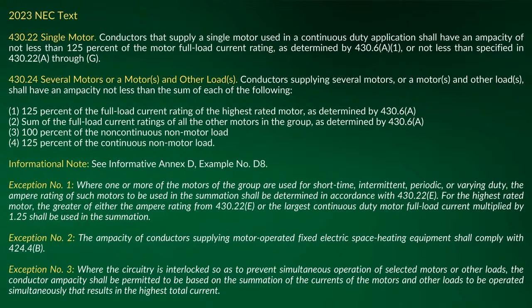Now we're going to look at the overcurrent device and see what it says. If I look at 430.22, I'm sorry, this is supposed to actually be 430.62 up top. I just didn't delete that first line up there. I was working on this at 3 and 4 in the morning last night, trying to get all this together. The haters are gonna destroy us over that. Now, if you look at 430.62A, it talks about a specific load, and what does it say?